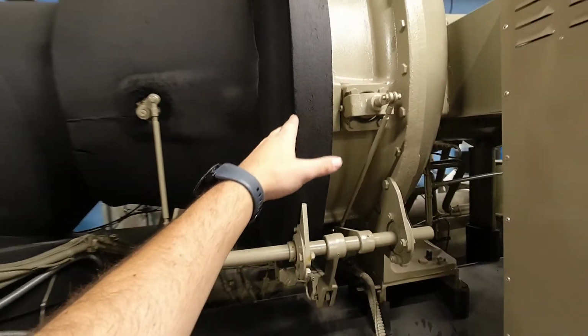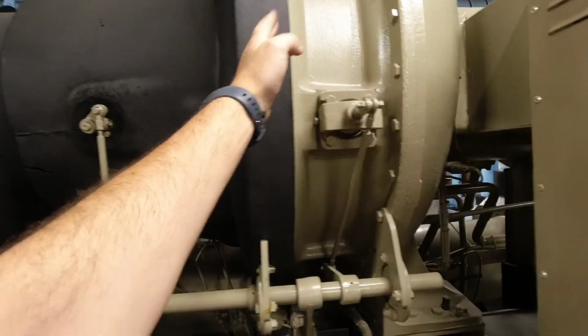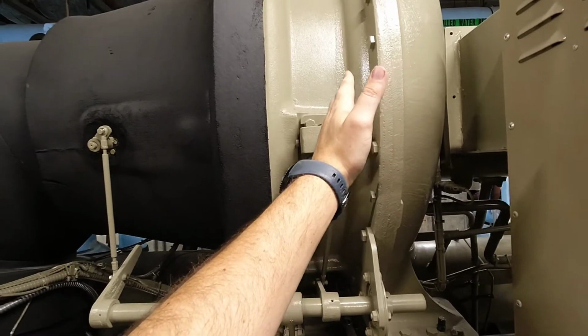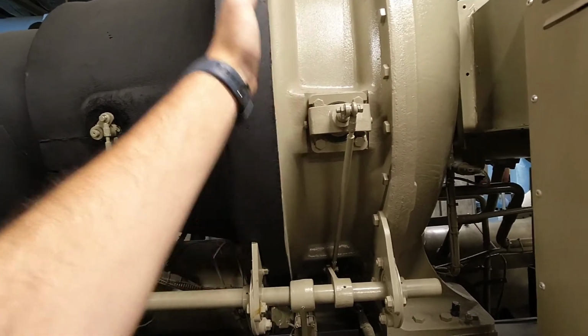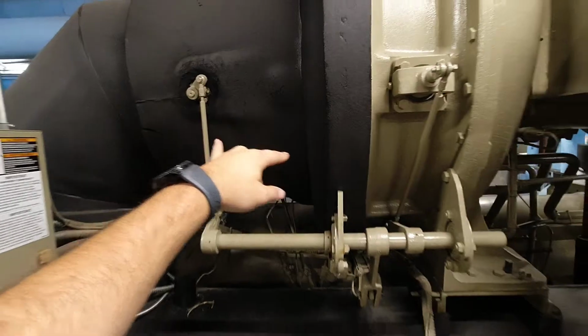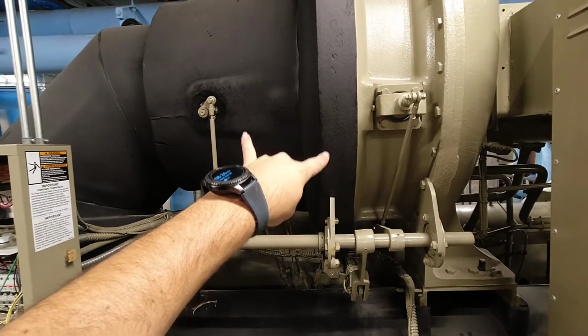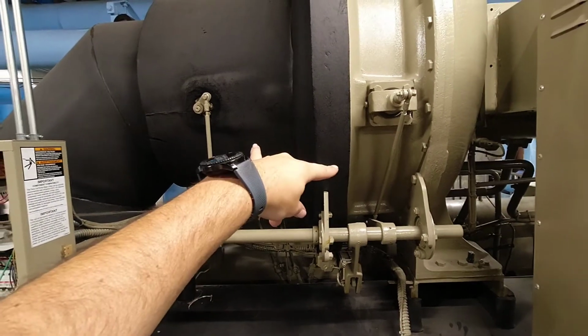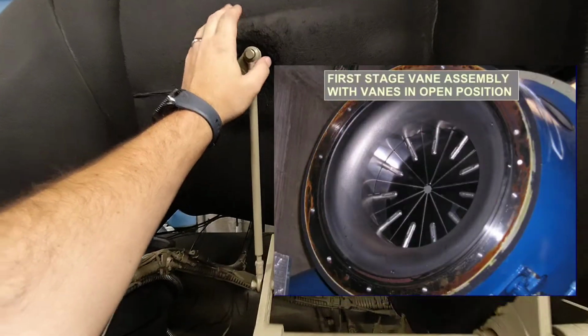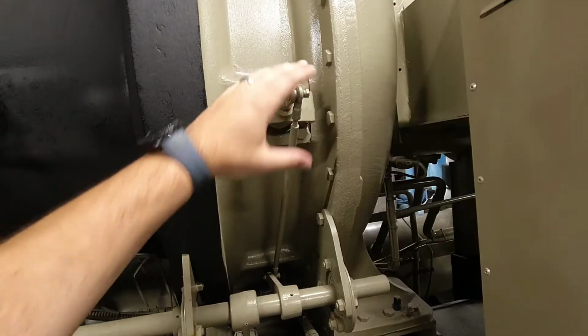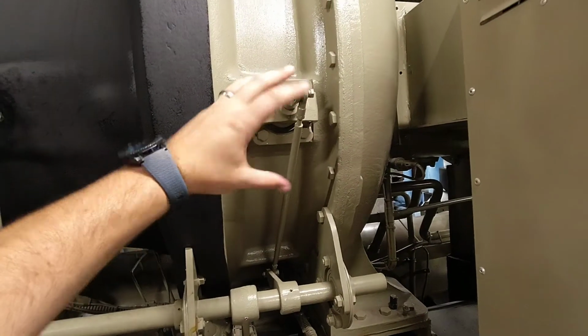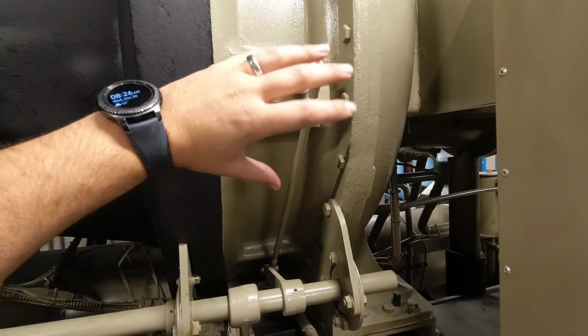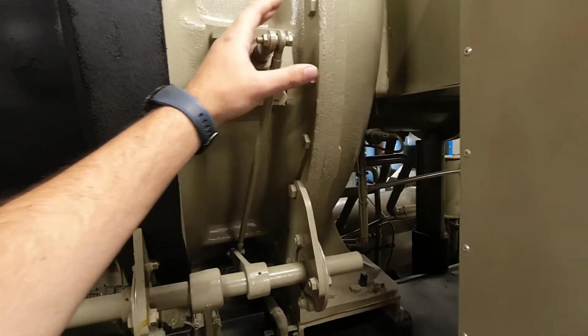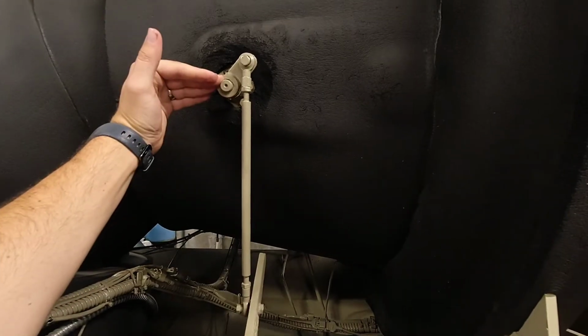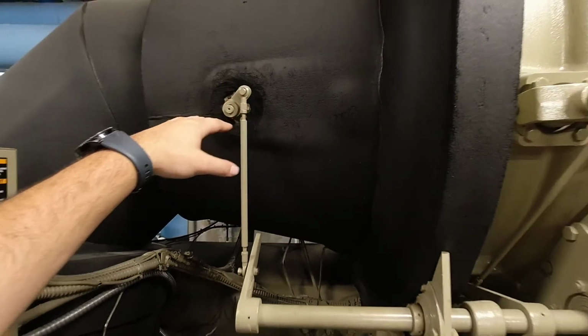This is a CVHF compressor, which means it only has 2 stages. A CVHE will have a 3rd stage in between. These Tranes, both series, use 2 guide vanes. This is a traditional style guide vane, and these are a little bit different style. Trying to think how to explain these. It's more of a rotor type style vane. These vanes' purpose is load control.